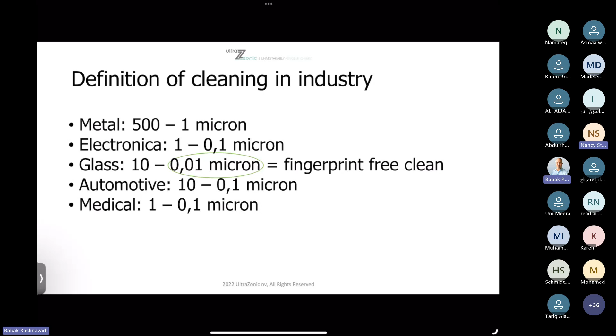Please go for the next. So some medical brands are using ultrasonic cleaning all the time, because they don't use any washer disinfector, because the washer disinfector is reproducible, but it's always with shadows. You have spray shadows because you have spray arms, and ultrasonic cleaning is really cleaning everywhere. Every little part of the instrument gets a decent cleaning. So like Storz or Draeger or Synthes or Martin, it's all made in Germany, and they all use ultrasonic cleaning equipment, but very advanced.